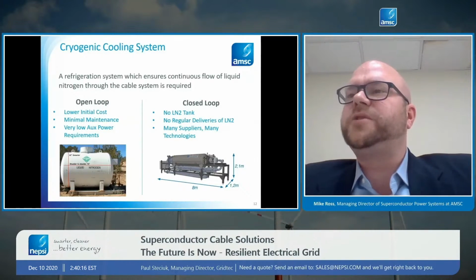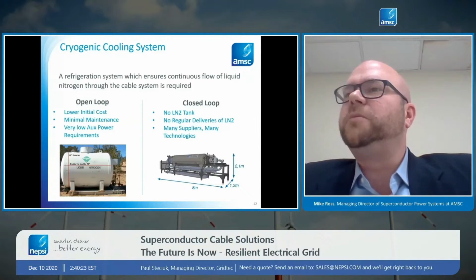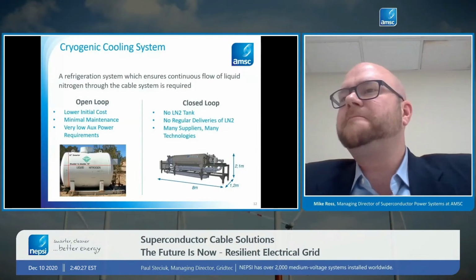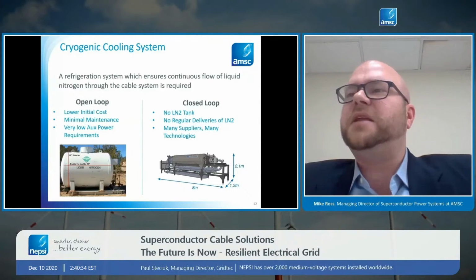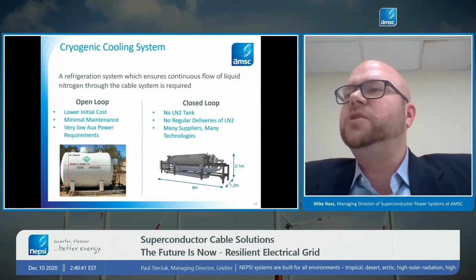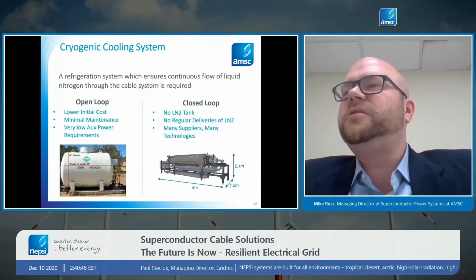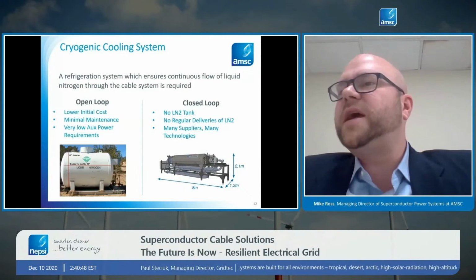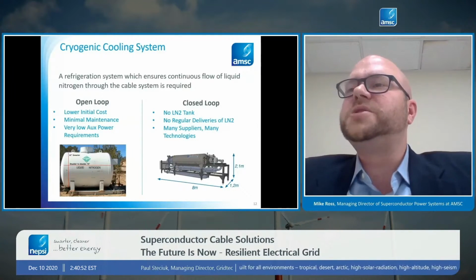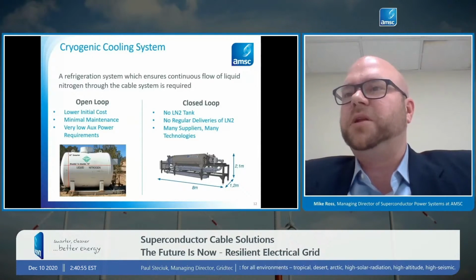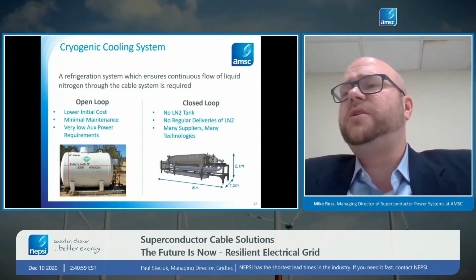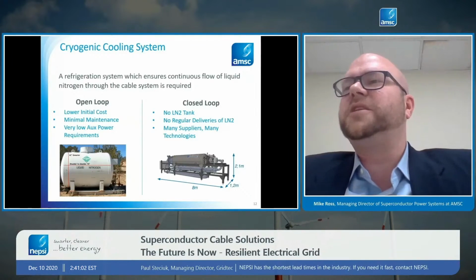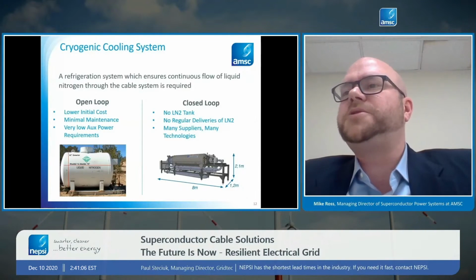And in that case, we have a refrigerator. So this slide is showing a very large refrigerator. This refrigerator is able to cool about 5 miles of superconductor cable. There are many technologies available, different sizes, different shapes, different cost points, different maintenance requirements that can be used to cool the cables. And in this case, you don't need a big tank. You don't need regular deliveries of liquid nitrogen, but you do connect into the auxiliary power. So you basically are using electricity to cool the cable instead of consuming liquid nitrogen. And for utilities, electricity is very plentiful and inexpensive. So their preference is usually to use this type of approach.